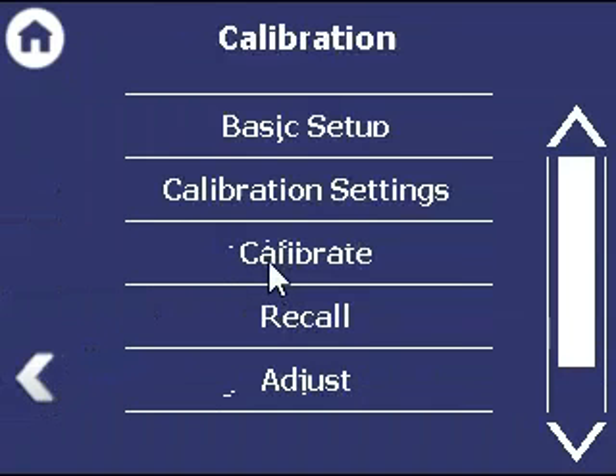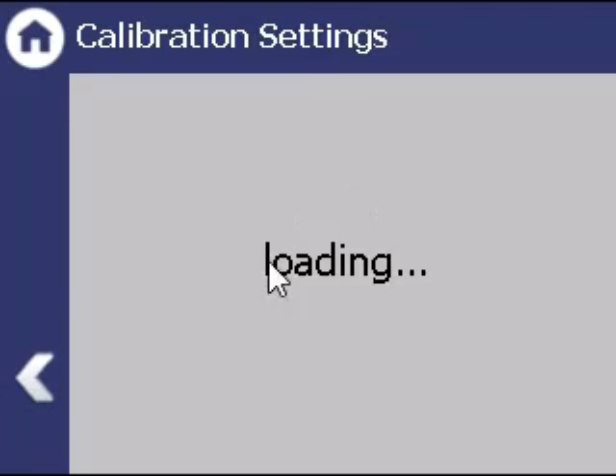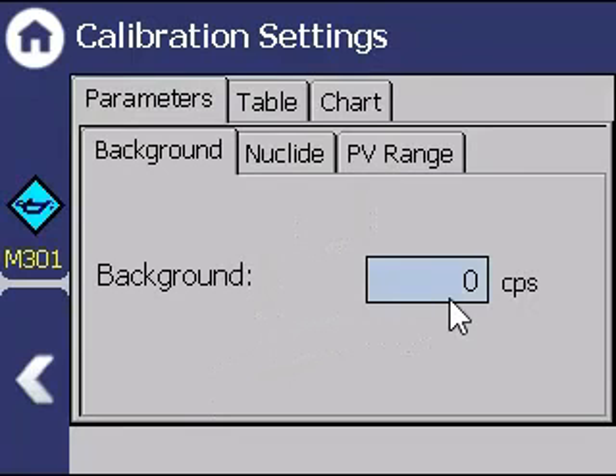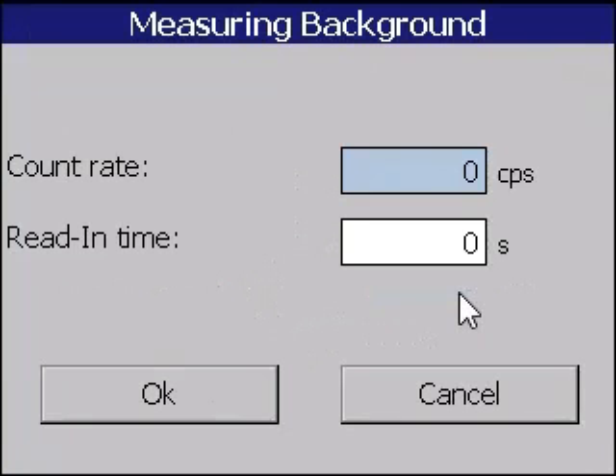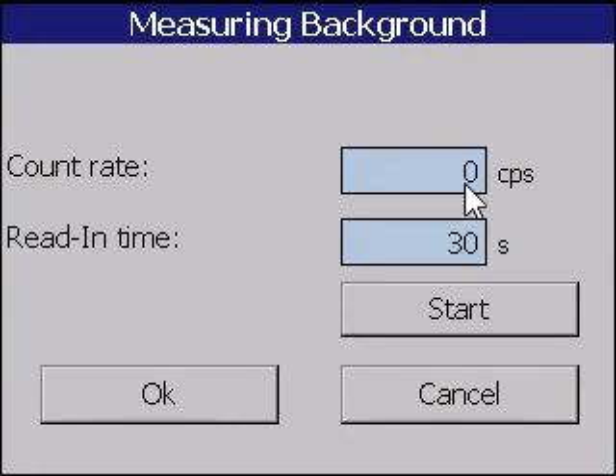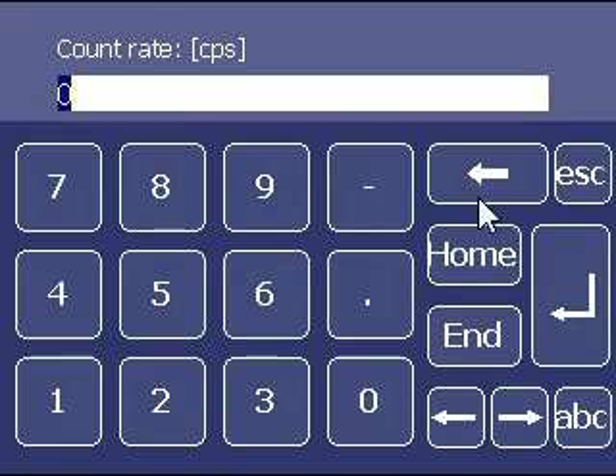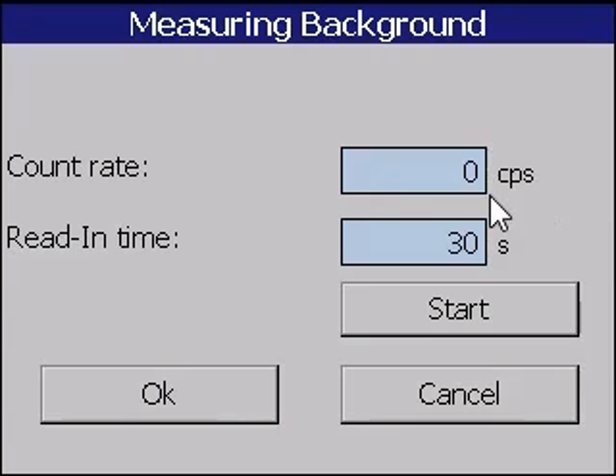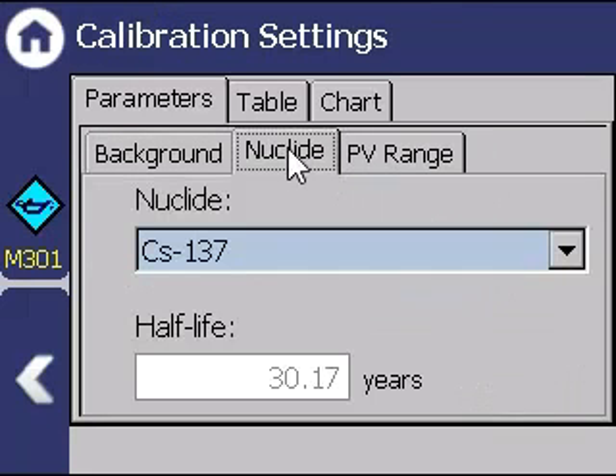Calibration. Calibration settings. Let's start with background. You will want to read in the background if your source has not yet been installed, so you can get an accurate measure of the natural background. If your source is already installed, contact a Berthold Service Advisor concerning your specific application. Select nuclide from the table and ensure you have the correct isotope selected as we alluded to earlier.